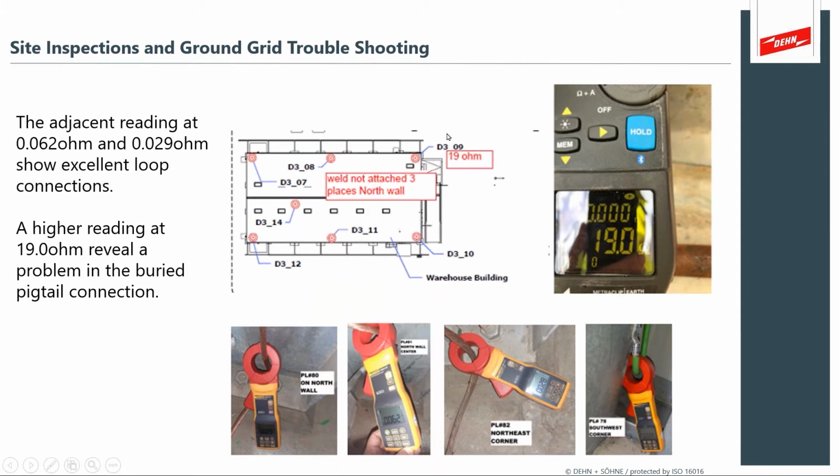This is helpful as part of your inspection and troubleshooting, because it tells you what to look for and where to go to find the problem. So in a system like this, you have your inspection records, and then you can come back and find these out-of-range readings that are the indicator that there's a problem, buried or unconnected.